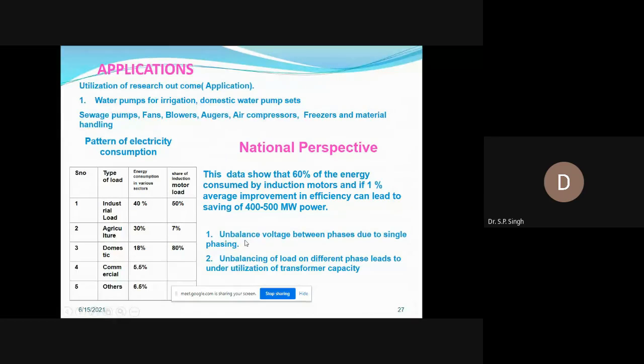So there is a problem: unbalanced voltage between the phases due to single phasing, and unbalancing of the load on different phases, leads to underutilization of the transformer capacity. This is a typical pattern; it's old data, but even now a lot of induction machines are in use.